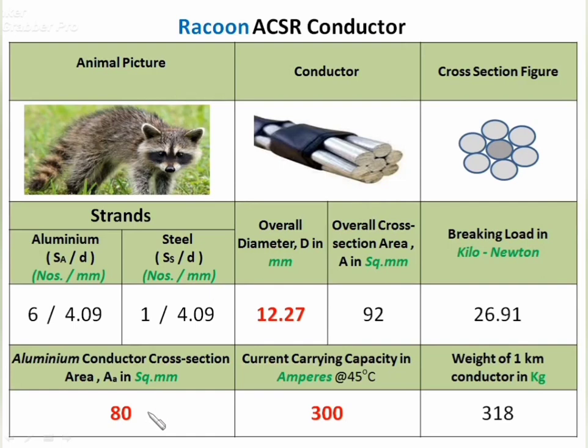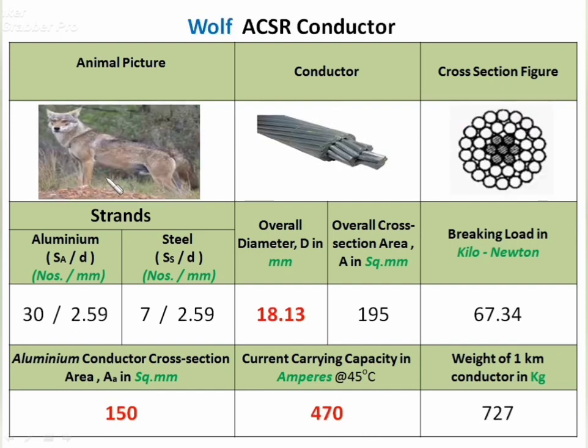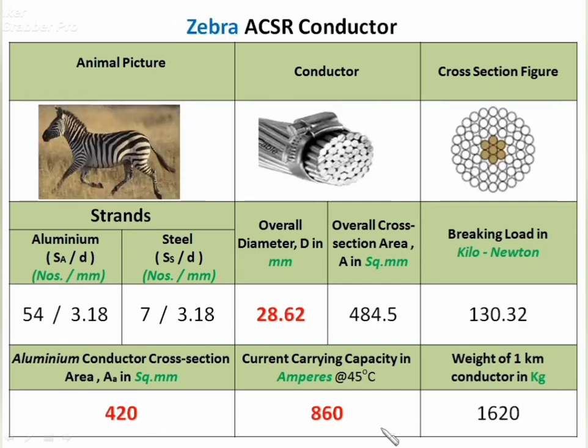Raccoon ACSR has aluminium area 80 mm² and 300 A current capacity. Dog ACSR — already discussed — has 100 mm² area and 360 A current capacity. Wolf ACSR has 30 aluminium strands of 2.59 mm diameter and 7 steel strands, with 150 mm² area and 470 A current capacity. Zebra ACSR has 54 aluminium strands, 7 steel strands, 420 mm² area, and 860 A current capacity.